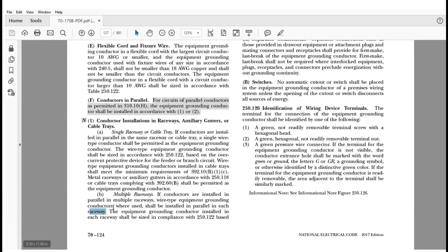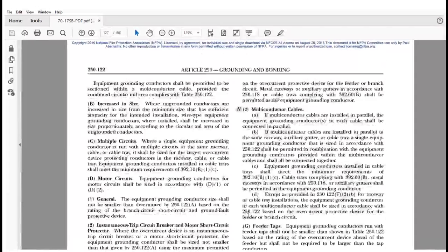Now, it says the equipment grounding conductor installed in each of those raceways shall be sized in compliance with 250.122 based on the overcurrent protective device for the feeder or branch circuit. So look, there's no paralleling here and reducing the size and whatnot. They're going to be full sized, they're going to be in each raceway, and that's the provision here.